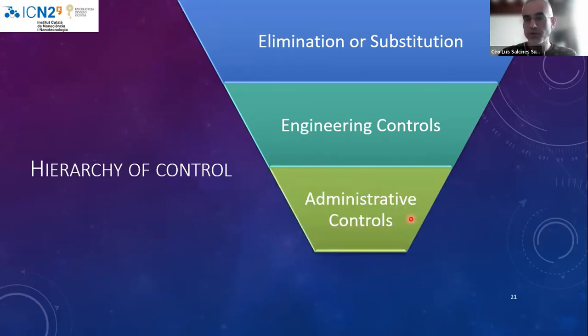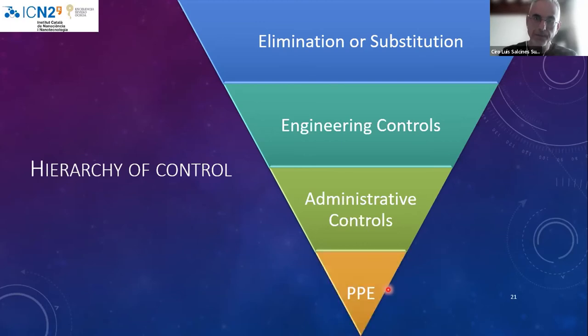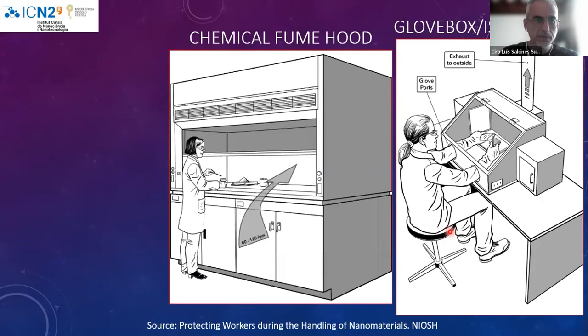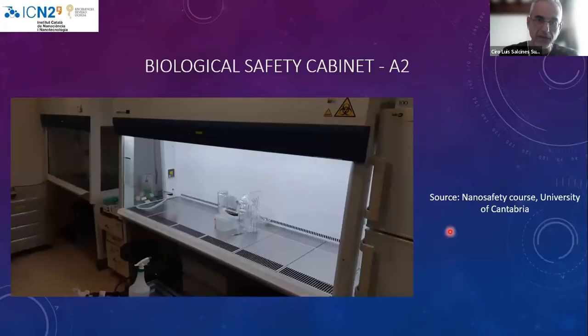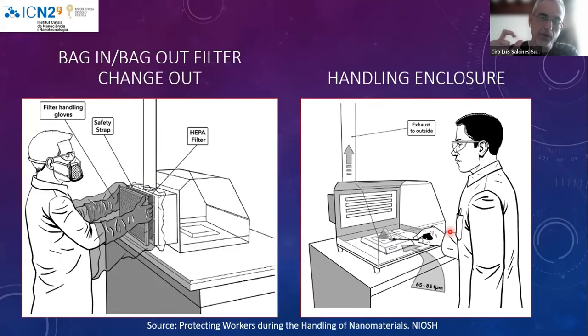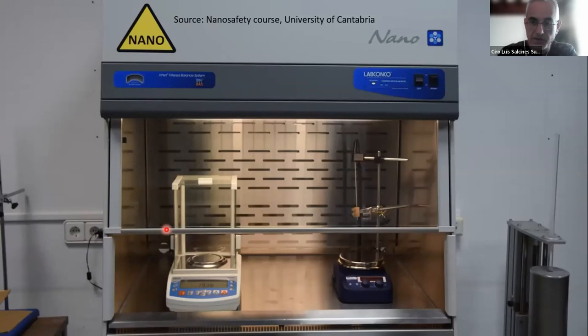Regarding engineering and administrative controls: it is not acceptable for anyone to use nanomaterials without knowing the details—without information and without training. Available engineering controls include fume hoods, biological safety cabinets, and nano chambers, which are a version of fume hood with low air speed that gives extra safety. When working with small amounts, handling enclosures can be used, with safe filter-changing procedures.